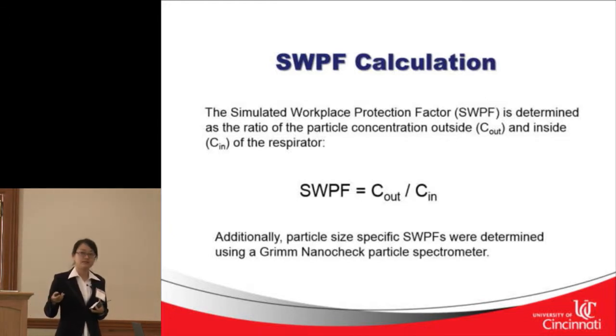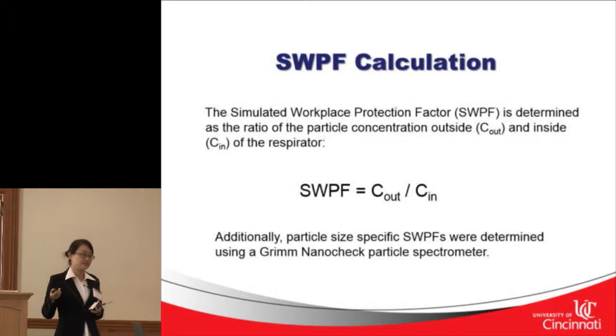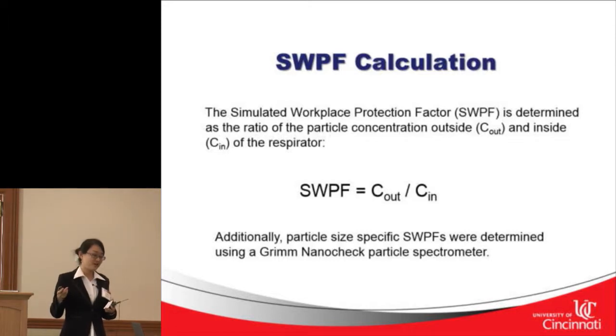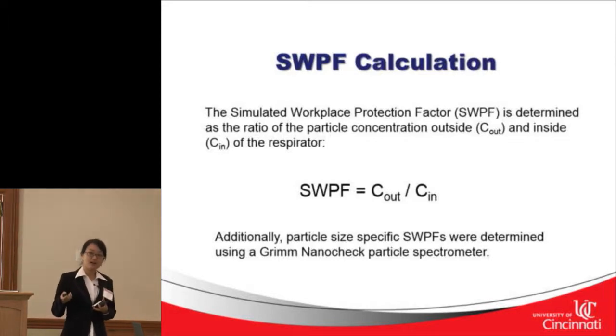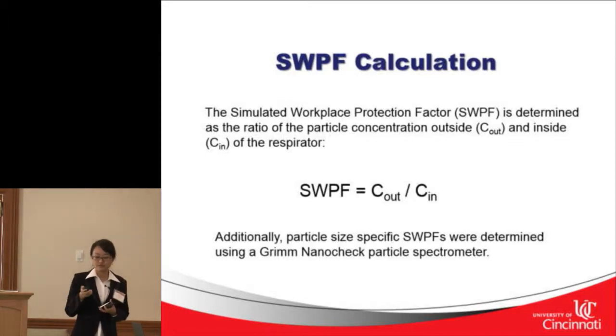The simulated workplace protection factor (SWPF) was calculated for each subject wearing each respirator, determined as the ratio of particle concentration outside divided by particle concentration inside. Because the device measured concentration by particle size, size-specific SWPF values were also calculated.